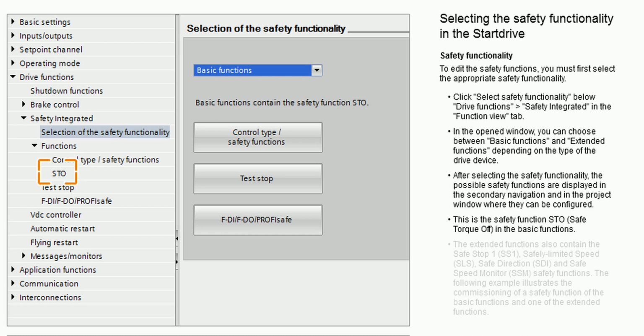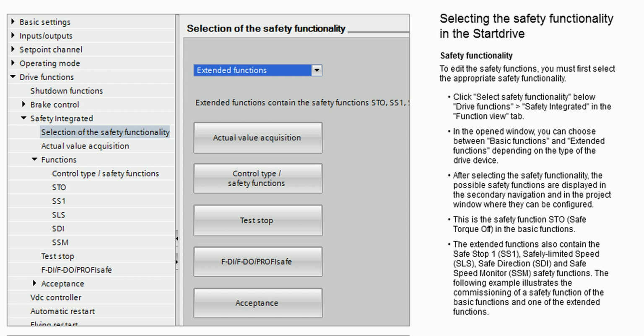This is the safety function STO, Safe Torque Off, in the basic functions. The extended functions also contain the Safe Stop 1, SS1, Safely Limited Speed, SLS, Safe Direction, SDI, and Safe Speed Monitor, SSM, safety functions. The following example illustrates the commissioning of a safety function of the basic functions and one of the extended functions.